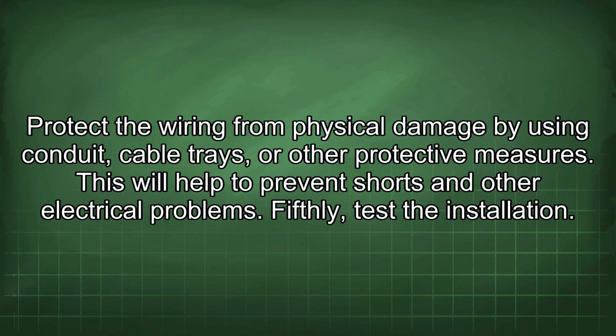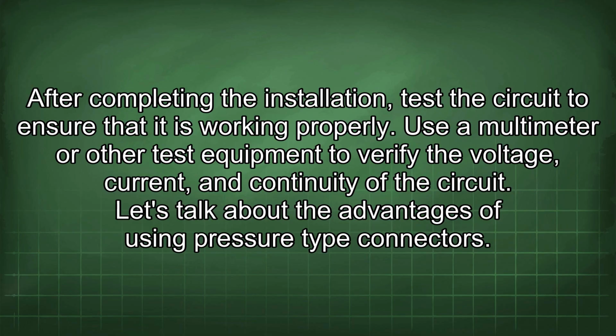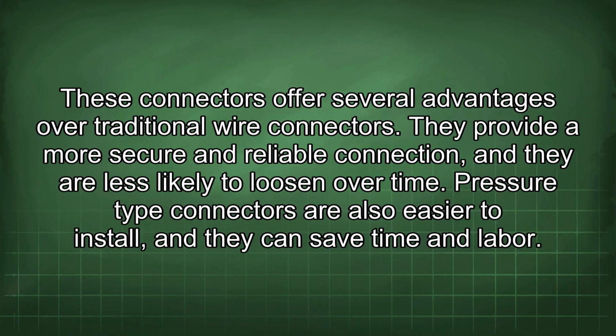Fifthly, test the installation. After completing the installation, test the circuit to ensure that it is working properly. Use a multimeter or other test equipment to verify the voltage, current, and continuity of the circuit. Let's talk about the advantages of using pressure-type connectors. These connectors offer several advantages over traditional wire connectors. They provide a more secure and reliable connection, and they are less likely to loosen over time. Pressure-type connectors are also easier to install, and they can save time and labor.